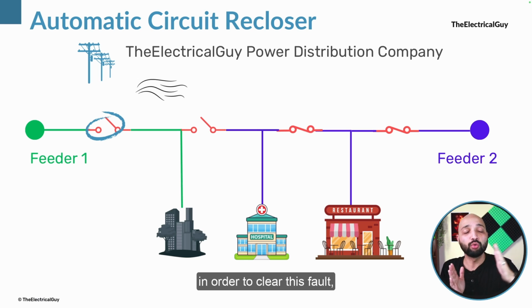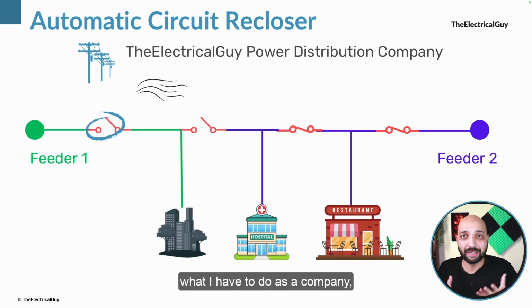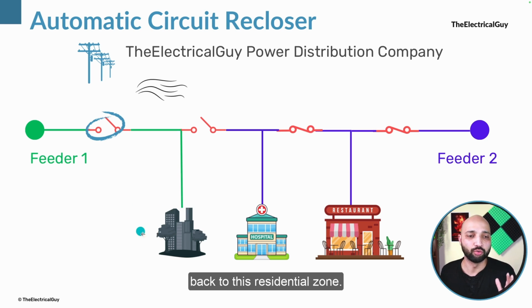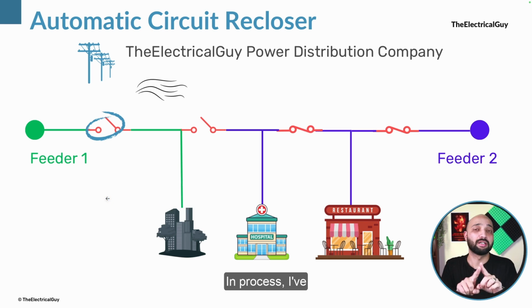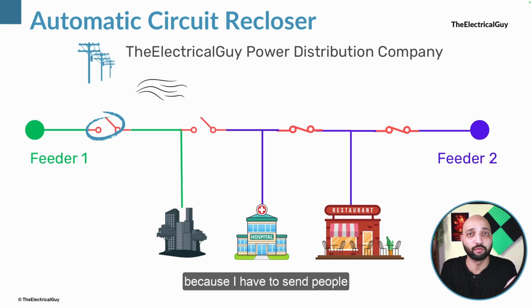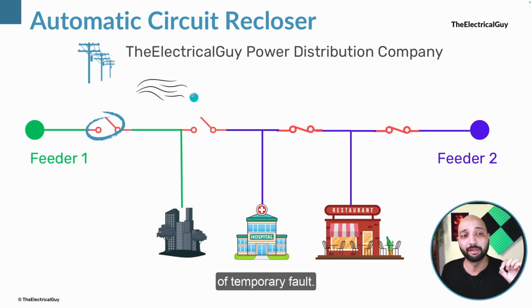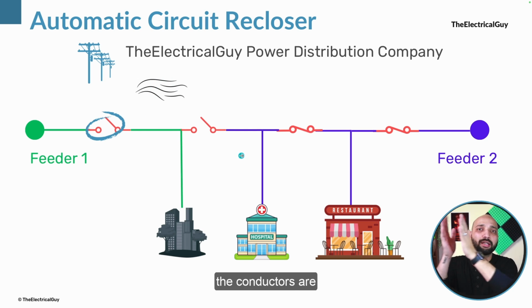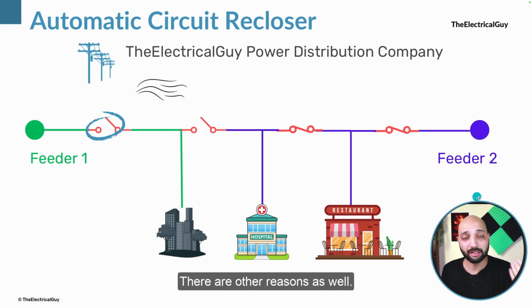Now, in order to clear this fault, as a company I have to send my engineers to the site, see what has happened, and then close the circuit breaker manually. Then the power will come back to this residential zone. In this process, I've of course lost time and cost, because I have to send people there and a lot of other things. So this is just one example of a temporary fault. High speed wind is blowing and the conductors are getting attached. There are other reasons as well.